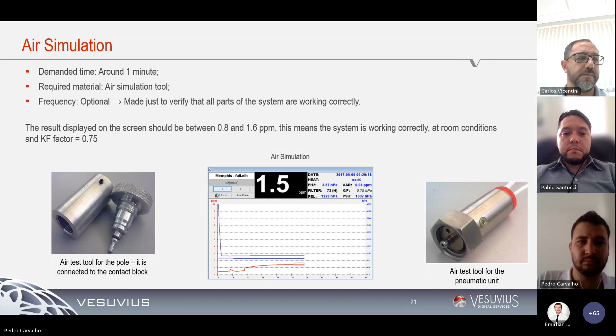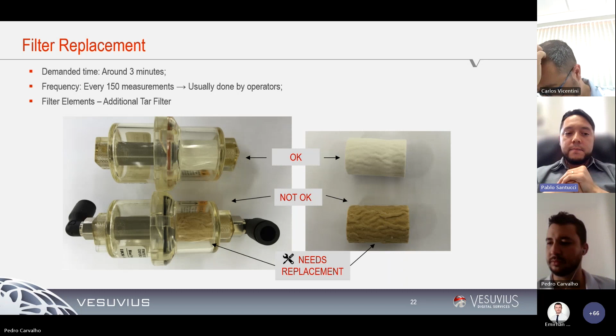And here is another recommendation that we would like to emphasize, which is related to our filters inside of the system. The frequency for changing them would be around 150 measurements, or any time that people or operations see that the filter element, as you can see in the bottom corner, right hand side, is in dark color. That requires a change in this case.